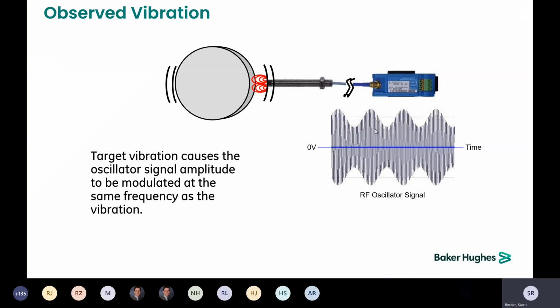So the very fast squiggly line here is the radio frequency oscillation from the Proximitor. As the material moves in and out of the range of the proximity probe, as it moves further away, we have less or full signal. As it moves into the field, it absorbs that energy as an eddy current.